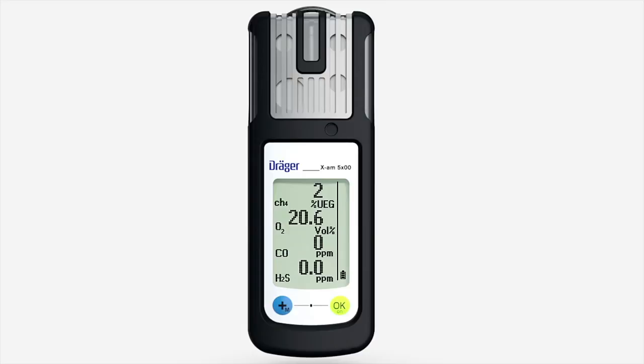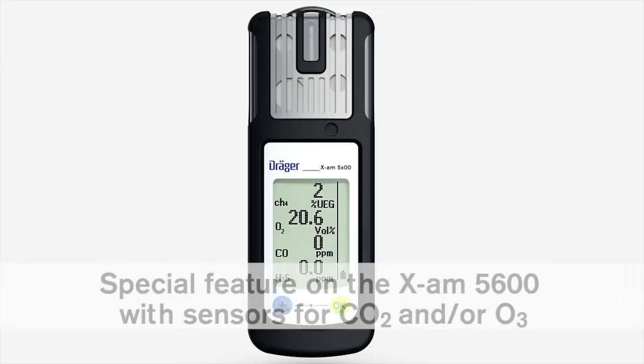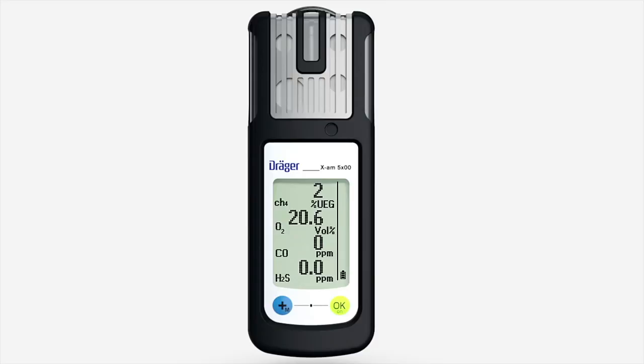The following additionally applies for the Dräger XAM 5600: the fresh air calibration and zero adjustment are not supported by the Dräger Sensor Dual IRCO2, Dräger Sensor IRCO2, or Dräger Sensor XXS O3. A zero adjustment of these sensors can be conducted using the Dräger CC Vision PC software.